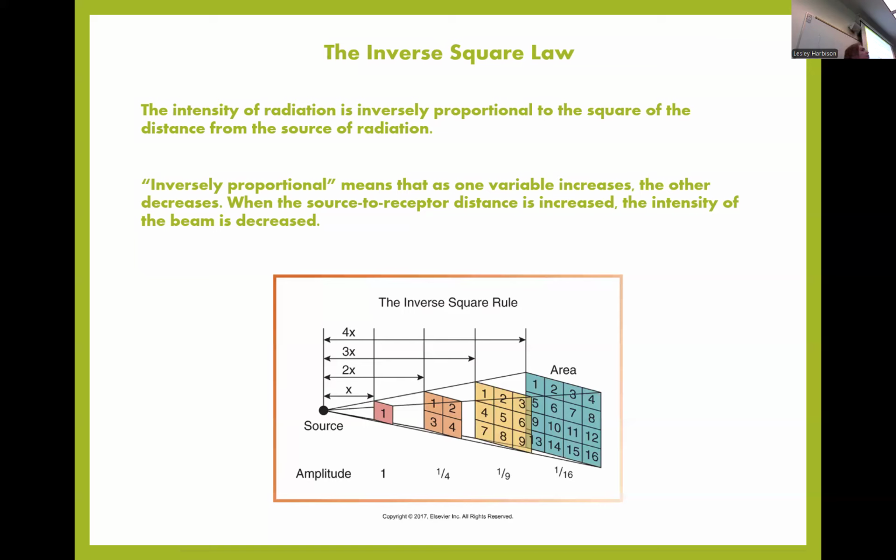Not going to get X-rays taken with the long ones? It actually, in theory, depends on collimation, which plays a role, and we'll get to that. But also the exposure time and the power. So this kind of makes you think shorter would always be better, but because we have different things inside the machine that help to control the spread, you can have a long PID and it's fine.